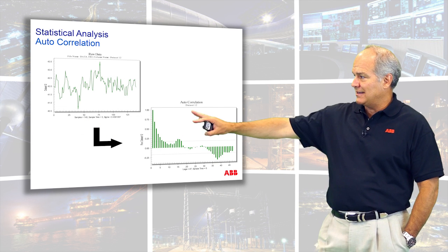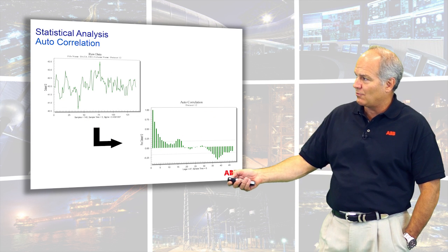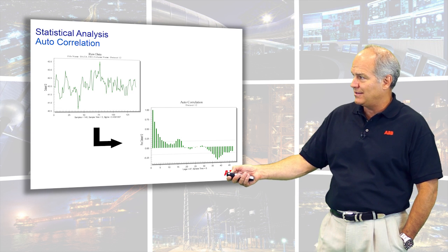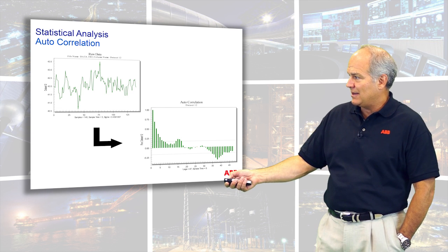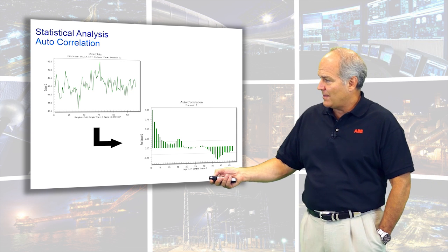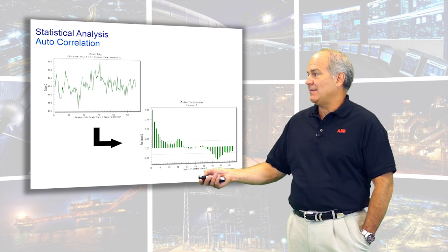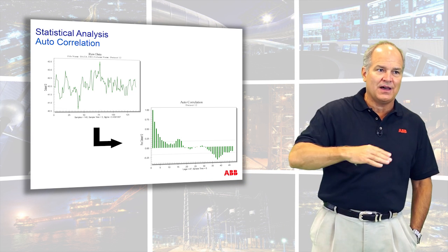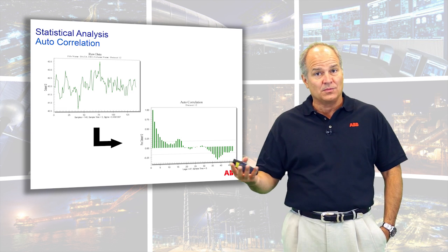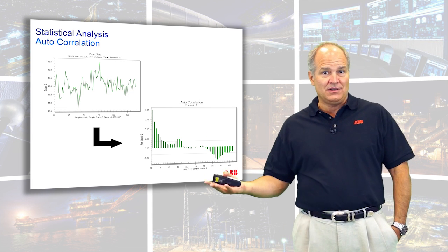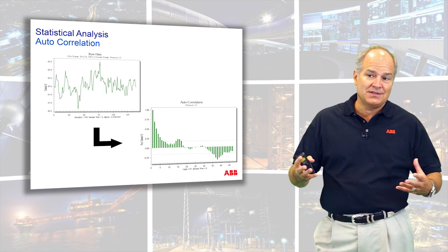Now here's showing an example, a real life example where we would take our raw data and run it through our autocorrelation. So you can see at lag 1, it's the same signal. This thing would have a signal-to-noise ratio of about a 0.75, and then it drops down to the confidence limits, but then it comes back up. Then it goes down and it shoots past. This is not normal, and it's got an energy signal that could either be tuning or it could be a process disturbance, either one.